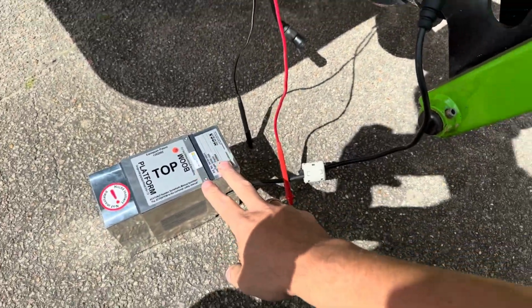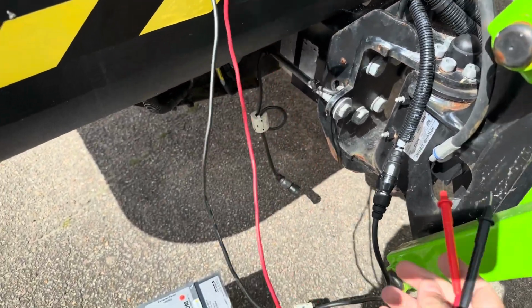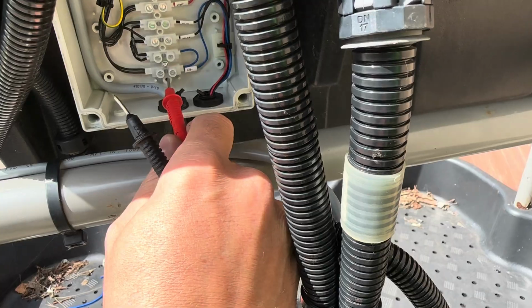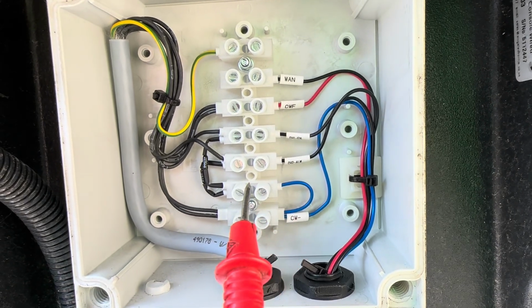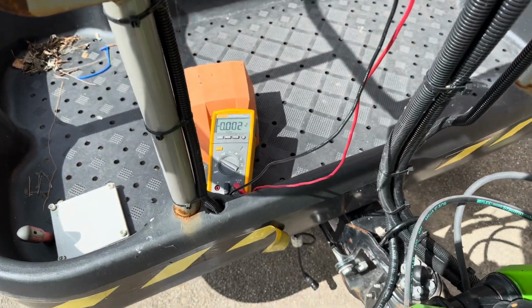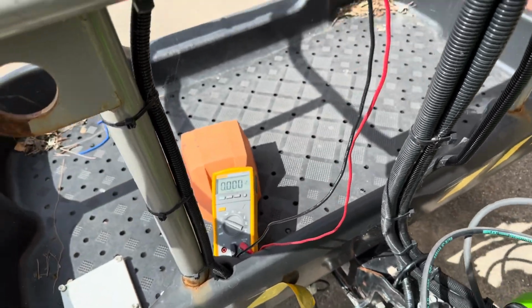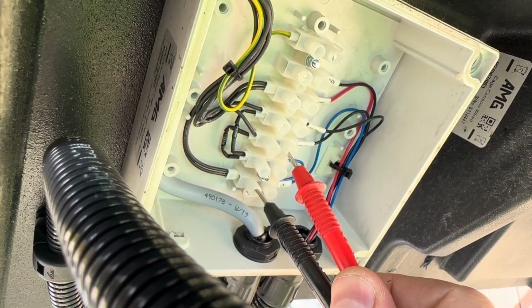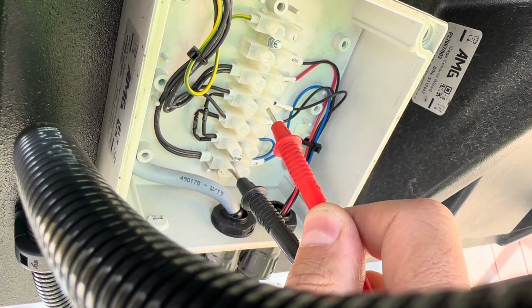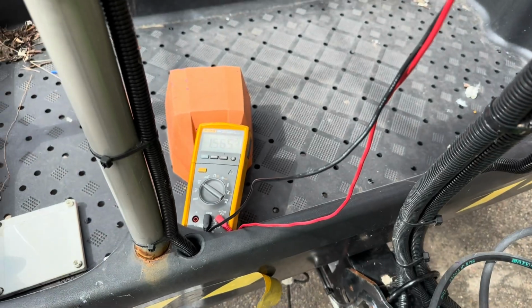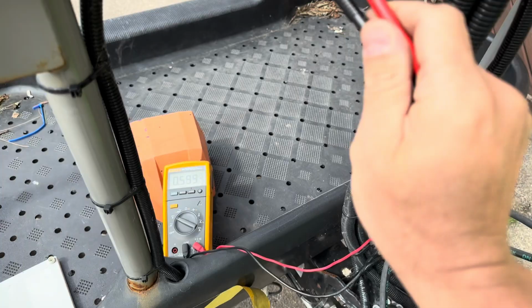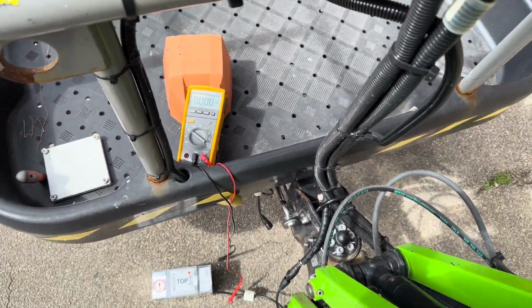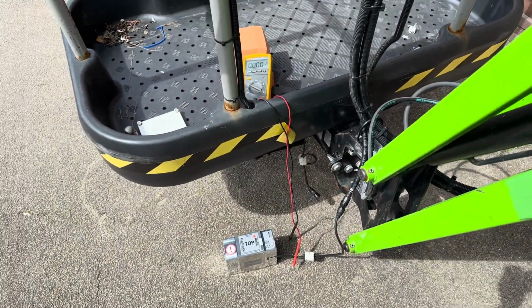So as a trial, I just put that cell outside here, connected in, and I want to check the voltage on channel 1, channel 2. So I will measure the voltage between the 0 and channel 1, channel 2. We're expecting to have the same reading. The original cell gives us quite a big discrepancy. So switch the machine on. The black one goes on the negative. Let's see if you can see it. And channel 1, I think that's channel 1. So that's what we're reading, channel 1, and that is 1.56. And channel 2, so I've gone one step up, that's 1.56 as well. So both channels are reading exactly the same, and that's the way it should be. Okay, so don't worry about the value for now. 1.56 is just because there's no load on the cell, it's just standing free there.